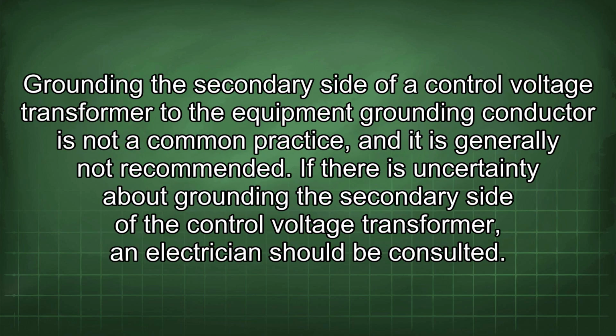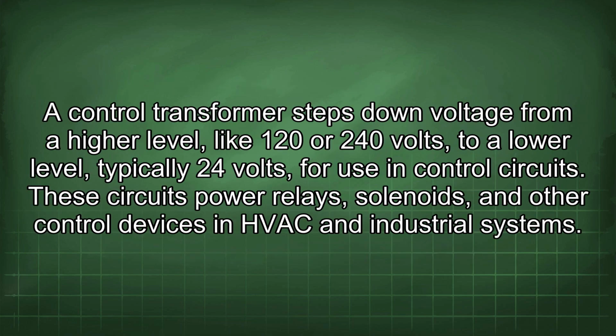Grounding the secondary side of a control voltage transformer to the equipment grounding conductor is not a common practice, and it is generally not recommended. If there's uncertainty about grounding the secondary side of the control voltage transformer, an electrician should be consulted. A control transformer steps down voltage from a higher level, like 120 or 240 volts, to a lower level, typically 24 volts, for use in control circuits. These circuits power relays, solenoids, and other control devices in HVAC and industrial systems.